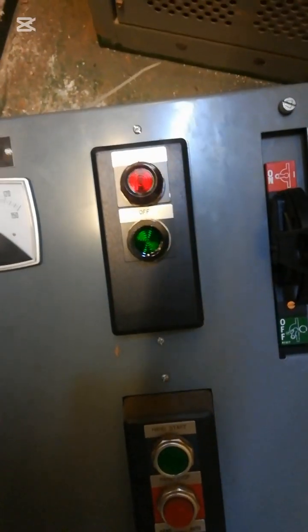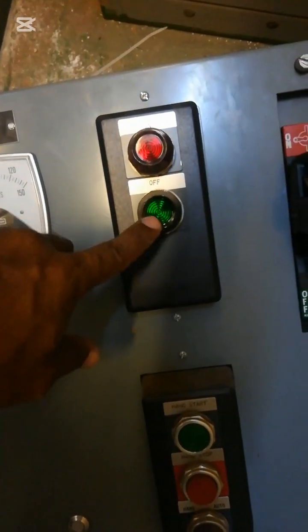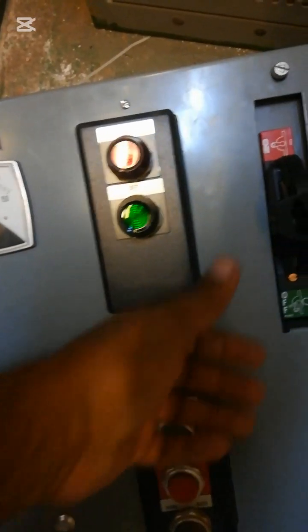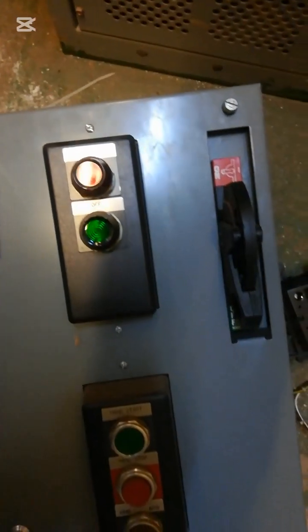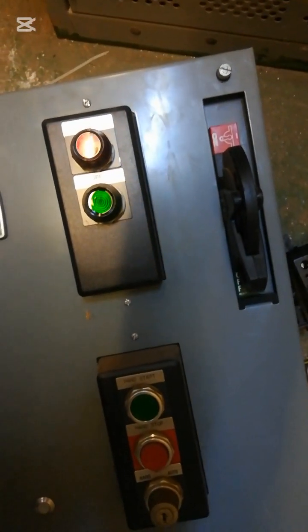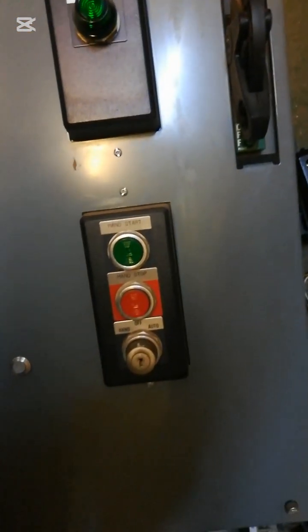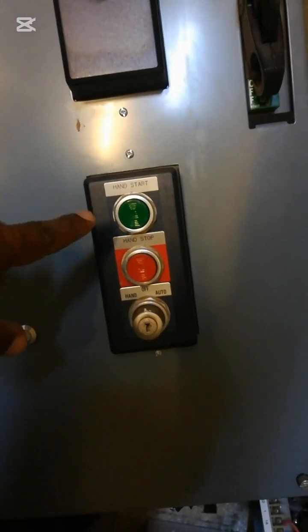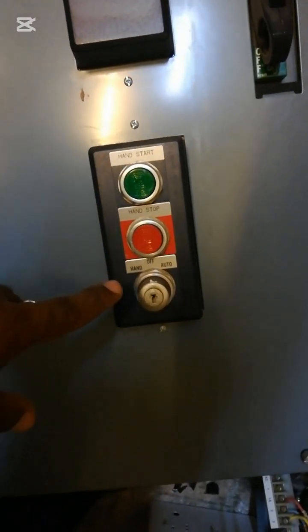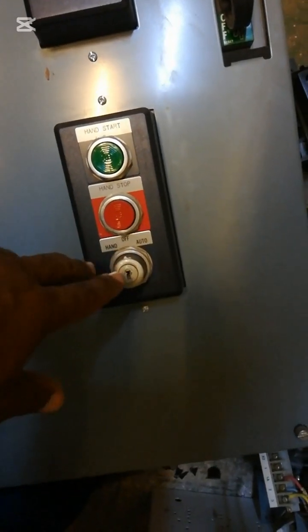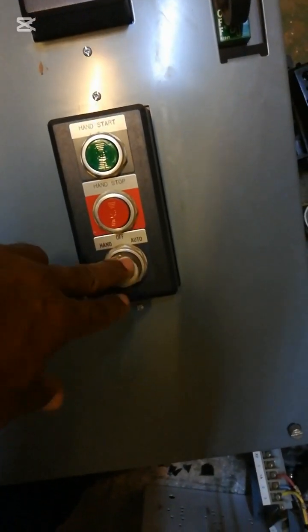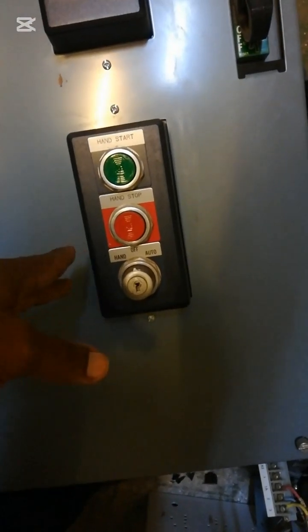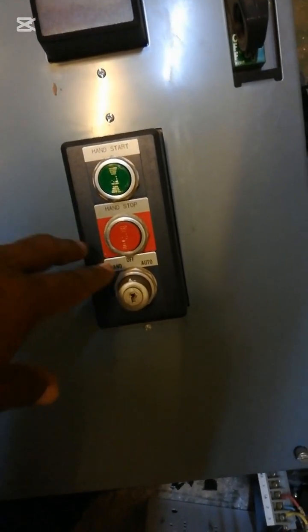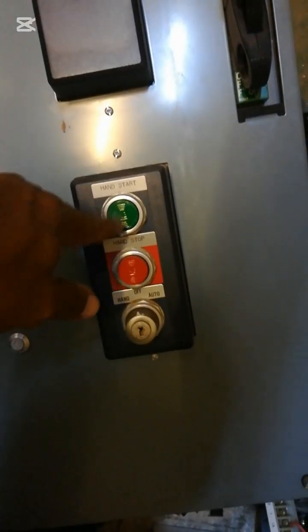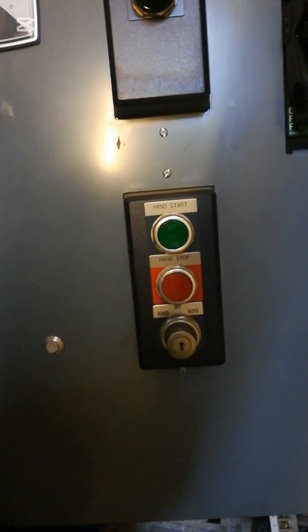Now the breaker would be up, the arm would be up at that moment to show that the power is on, and so the green light would be showing. If the breaker, that's the arm for the breaker, is down, then the green light will come off showing that it is de-energized. You also have hand start and stop, and you have a selector switch that you can put in hand. When it is in the hand position, it will mean that you can stop and start it by either the local push button here, which is on the panel, or from a remote out in the field.